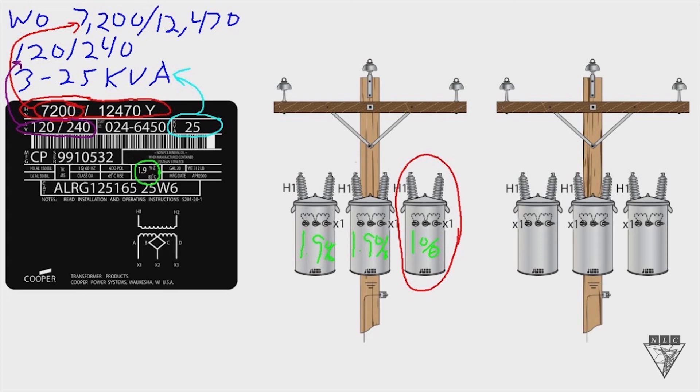Okay, so the last part of the equation is the polarity. And I'm going to circle it, it's right here in the middle. And you want to try and find three transformers that have the same polarity. In this particular case, our transformers show additive polarity.